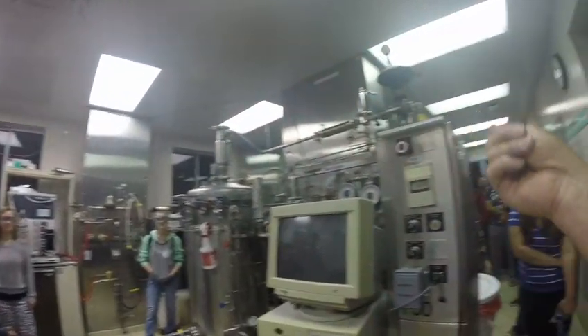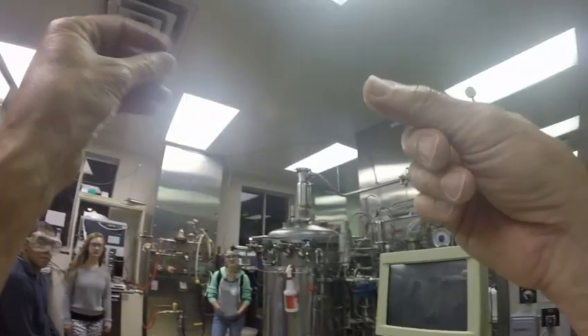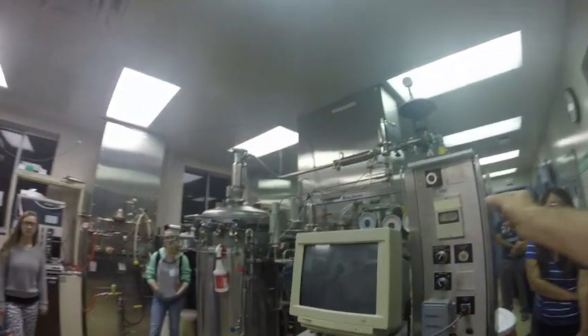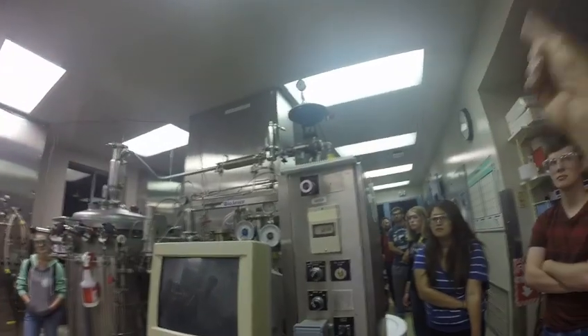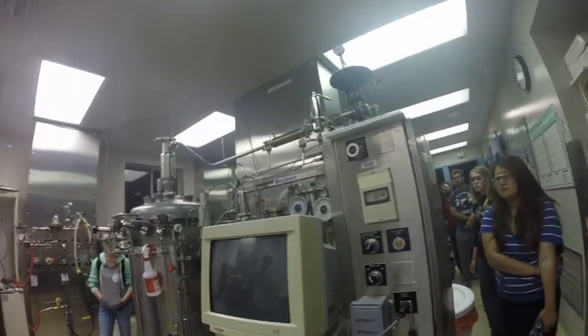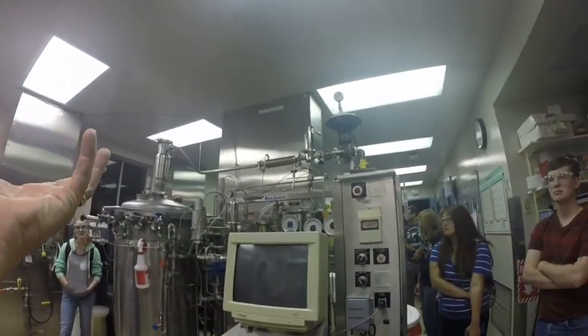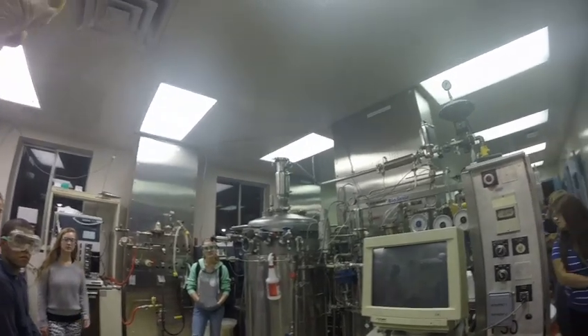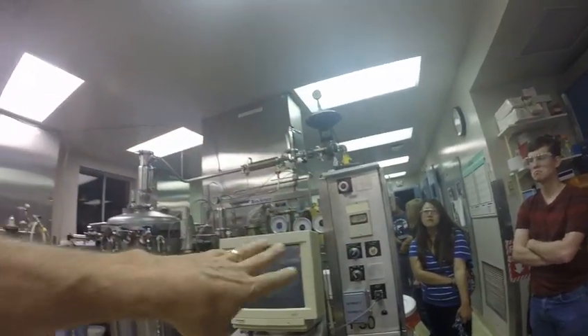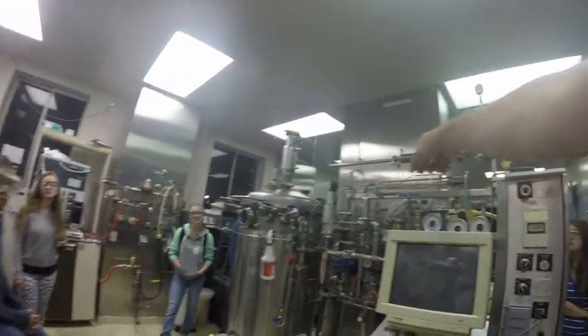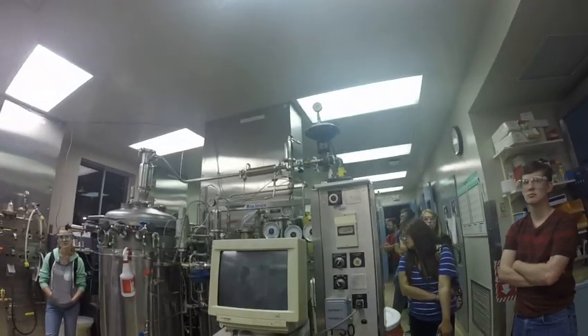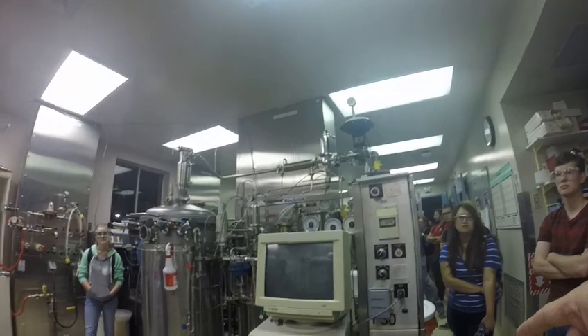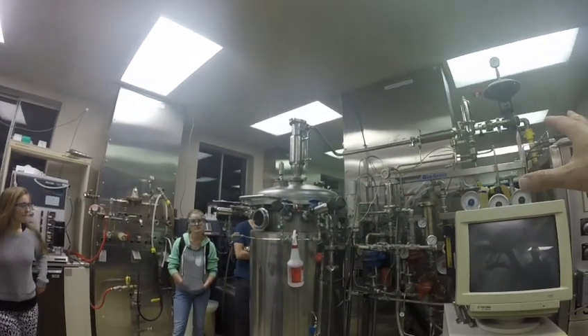And it is. A Tempilstik is a crayon whose melting temperature is 121 degrees Celsius. It has a little bit of graininess to it so that if you put it across a piece of stainless steel, it kind of grates. But as soon as it reaches its melting point, it does a nice smooth thing like that. That Tempilstik will be part of your SOP because it gives you an entirely independent way of knowing that you in fact made that temperature, because just because you open the valve doesn't mean that some other valve didn't let steam get to the thing you were actually working with. And that's part of understanding that there's a strong degree of redundancy in the actual operation of the unit itself.